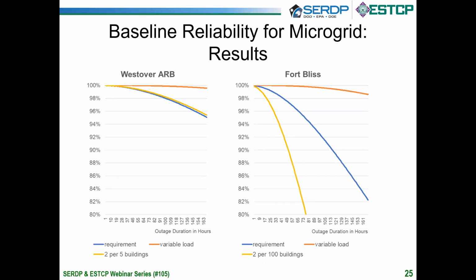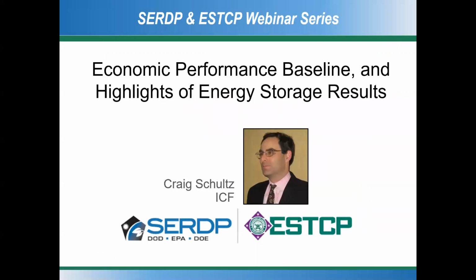But if you look at the performance of an actual diesel microgrid under variable load for this base, it's up at 99+% during those hours. So these set the performance requirements that we wanted to compare an advanced storage-enabled microgrid to. Again, we're not setting the baseline as what would be performed by standalone generators. We're setting it by what would be performed by a diesel-only microgrid. Now, let me turn it over to Craig to discuss the economic baseline and highlight the results that have been achieved in phase 1. Slide 26.